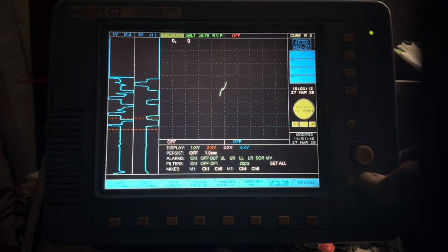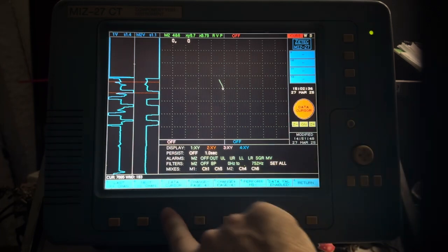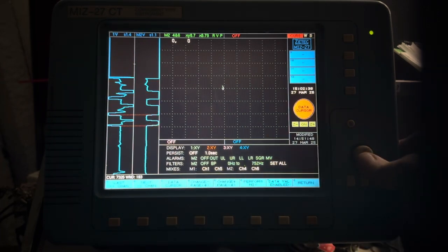Now, to size these types of indications, a lot of times they'll use a mix. And I have already created a mix for this channel. And what you normally do with the wear scars, I'm going to put a mix channel 2 up here. Mix 2 vertical, okay. We normally take those flaws and we vector them upwards, up vertical. I need to increase my span so you can see that one.